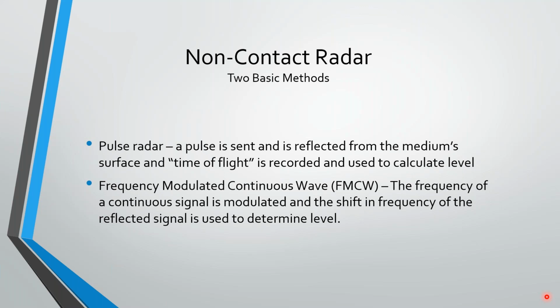There's something called pulse radar, which works very much like guided wave. We send out a pulse, we wait for it to be reflected, we look at the time of flight, and we calculate the level. And then there's something called FMCW, or frequency modulated continuous wave. With this type of technology, we send a continuous signal, but as we're sending the signal, we're modulating the frequency. So we're not only looking at the amount of time, but we're also looking at the shift in frequency. This is a superior way of doing things because there's less chance of having a loss of signal. And also, if it's a very long measurement, there's less chance of introducing a lot of noise if we're doing this constant signal. So we'll talk about both a little bit.